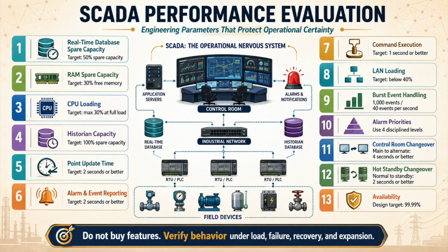And engineers should not test only the cleanest graphic. They should test the heaviest and most demanding displays, because that is where performance weakness appears, especially during startup, shutdown, trip recovery, valve lineup, sequence operation, and emergency response.